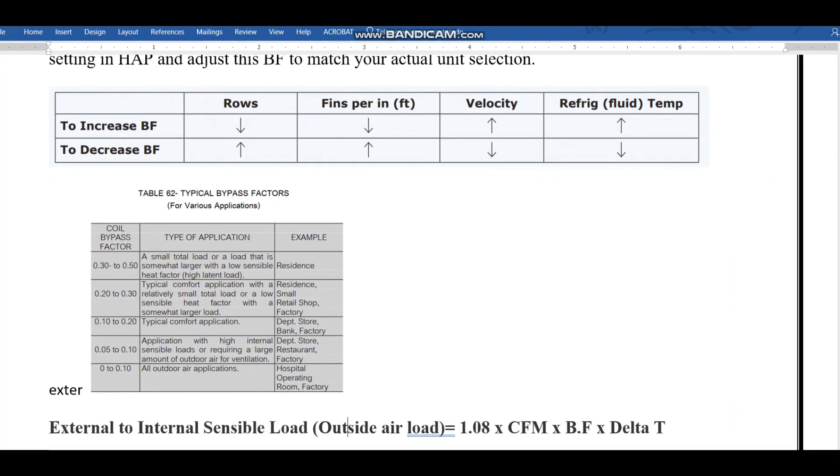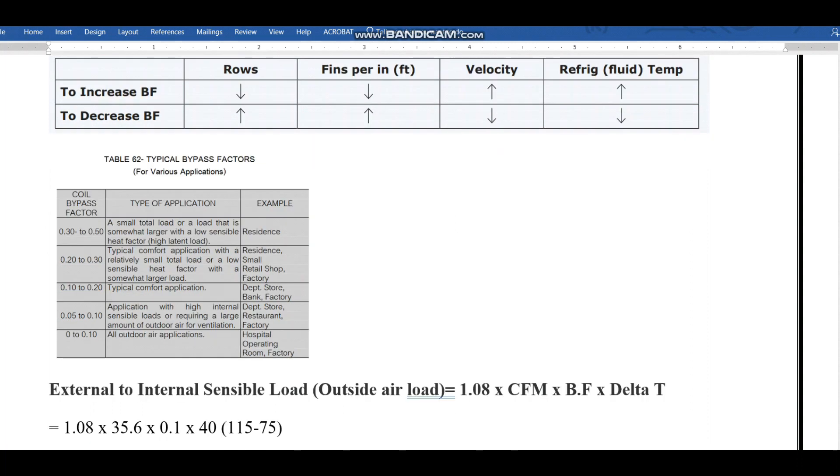The reference for this table is Carrier handbook. In this table, the bypass factors are given for different applications. For example, hospital operating room bypass factor will be very low, 0 to 0.1. If you go to small retail shops, the bypass factor can be 0.2 to 0.3. Normally we consider 0.1 in the initial tender stage as a default bypass factor in the HAP calculation. Later stage we can modify based on the selection.